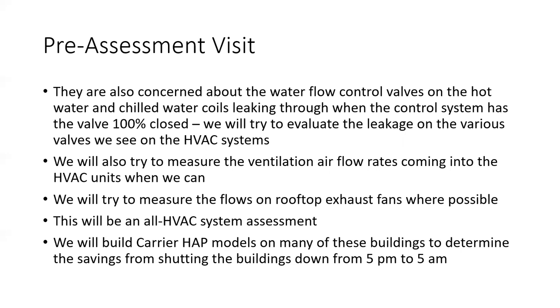We will have a walkie-talkie supposedly, and we'll call up to the control room and tell them where we are, and we'll tell them, okay, close the chill water valve. And so they'll close it on the computer, and then we'll give it a few minutes and see if the air temperature changes, see if we can detect a change in the temperature of the pipes, if we can get a thermocouple probe in there to try to figure out if the valve is leaking through. How this is going to go, I have no idea. We're just going to have to roll with the punches.